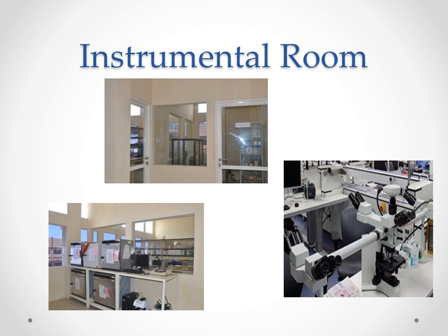The instrument room should be kept neat and clean as most sophisticated instruments are stored there. It should be air-conditioned to make it dust-free, reduce humidity, and avoid high ambient temperature. Otherwise, dust accumulation and high room temperature decrease the longevity of instruments. High humid conditions can also cause rusting of metallic components and fungal growth on optical parts such as microscope lenses and phototubes of spectrophotometers.